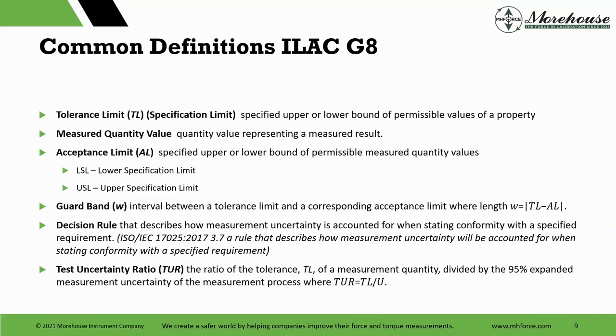Measured quantity value is the quantity value representing a measured result. Acceptance limit. So what we typically have, we're going to have an LSL, lower specification limit, and a USL, upper specification limit. It can be one-sided. Most instruments that we see generally, if this audience is for force, have dual-sided limits, meaning you have an upper and lower specification limit. Then we're going to discuss guard band, and that's an interval between a tolerance limit and a corresponding acceptance limit. And decision rule. A decision rule describes how measurement uncertainty is accounted for when stating conformity with a specified requirement. And then ISO/IEC 17025 says the same thing, how measurement uncertainty will be accounted for when stating conformity with a specified requirement.